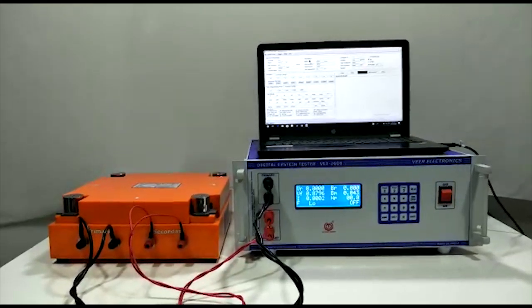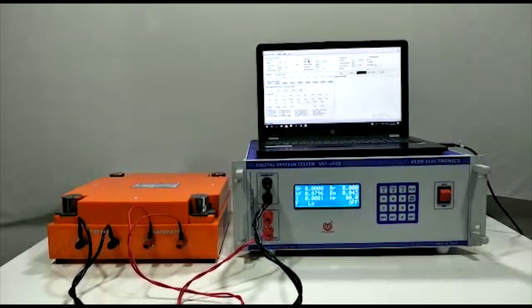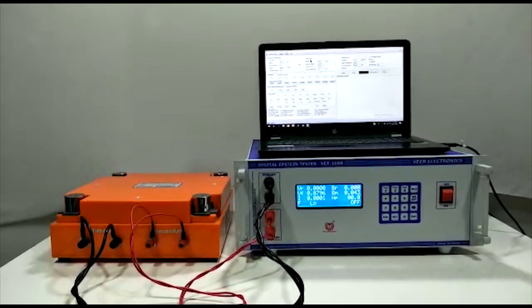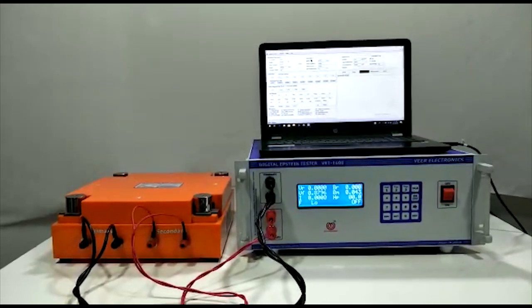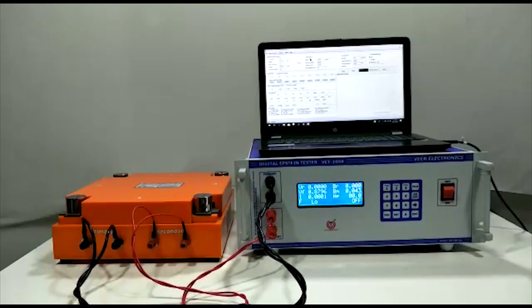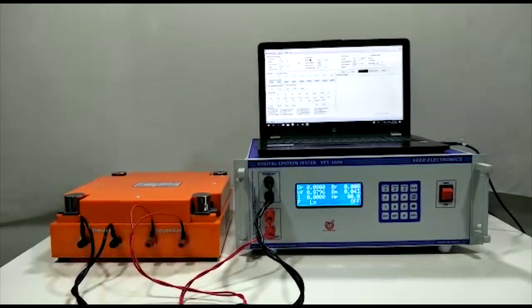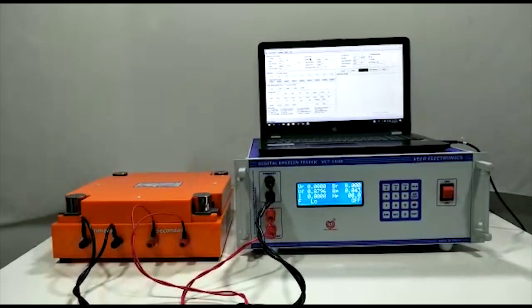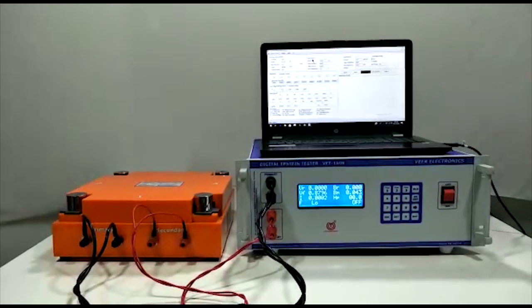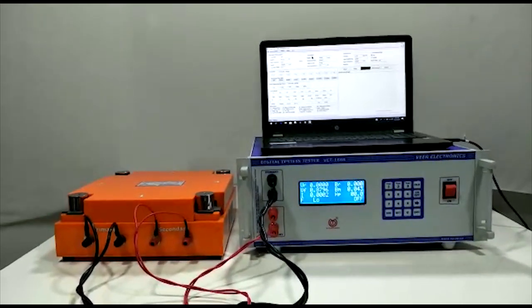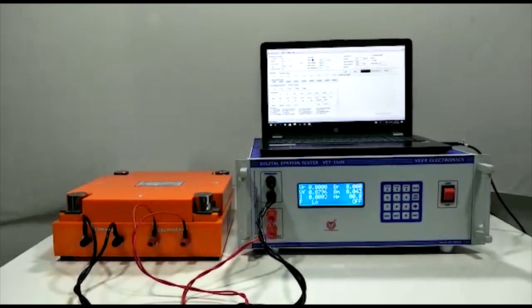It gives watt per kg, VA per kg, magnetizing force, permeability, and hysteresis curve or BH curve of the electrical steel at various induction levels.